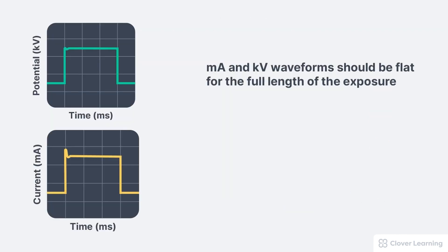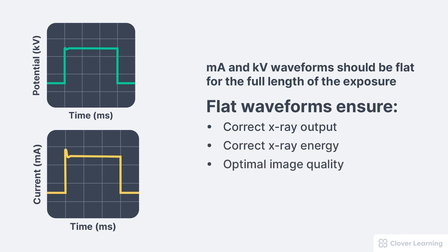So in summary, both the mA and kV waveforms should be flat for the full length of the actual exposure. This is important to ensure correct x-ray output, correct x-ray energy, optimal image quality, and optimal patient dose.